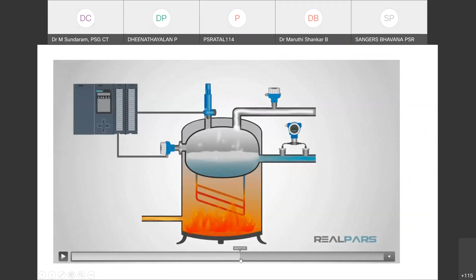See, this kind of thing is used in building automation and in a lot of filtration tanks, industries, compressors, air conditioning, centralized air conditioning, coolers, chillers, refrigeration, heat ventilation, air conditioning, cold room storage, several places. Here the pressure is more, but when dust occupies this filter, this side pressure is going to be less. So this differential pressure, comparing this and this, always shows the difference. When this difference goes beyond a certain limit, it will automatically indicate yes, there is a choke in the filter which is to be cleaned.